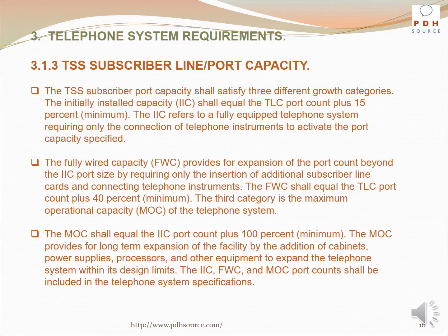capacity specified. The fully wired capacity, FWC, provides for expansion of the port count beyond the IIC port size by requiring only the insertion of additional subscriber line cards and connecting telephone instruments. The FWC shall equal the TLC port count plus 40% minimum.